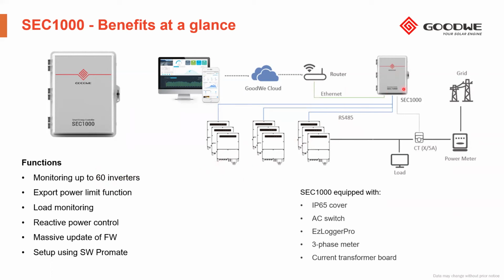And we do it by 485 communication line. We can limit the export power of the PV plant to the grid, right? Here is a basic example. Obviously, it's a three-phase application. This is only an explanatory diagram, obviously. But by means of these CTs, that is current transformers, the SEC 1000 will control the import and export power flow. So with this device, we will be able to control the export power to the main grid, right? In some markets, depending on the norm or legislation, it is not allowed to export energy, or an amount of energy, to the grid. So this device gives us this function as well.